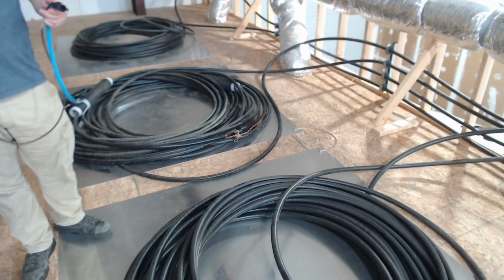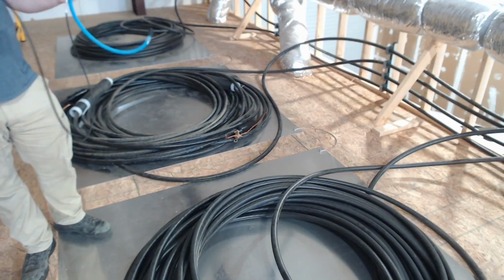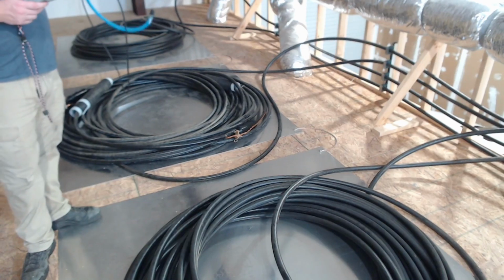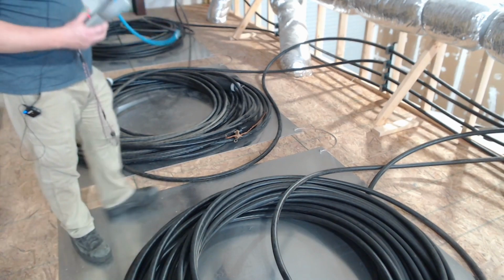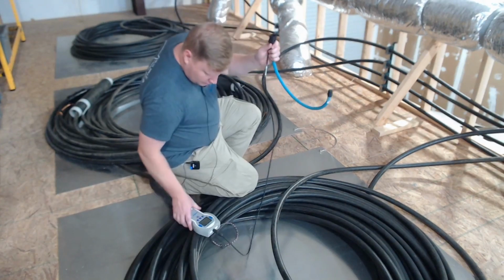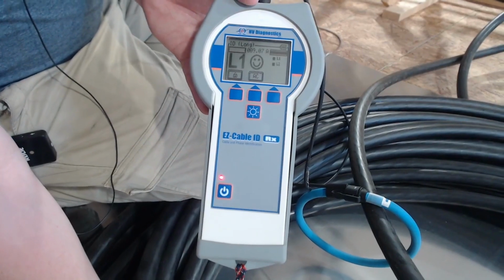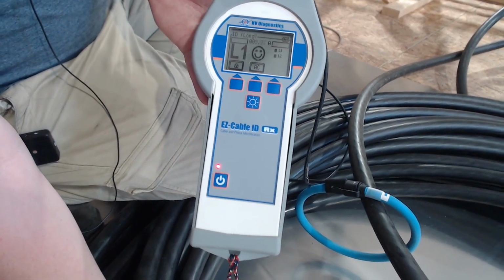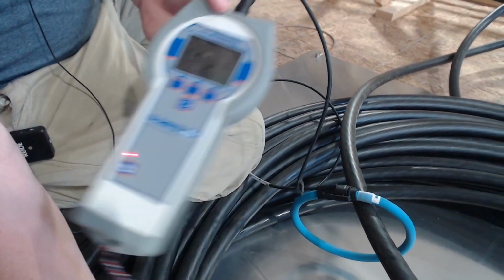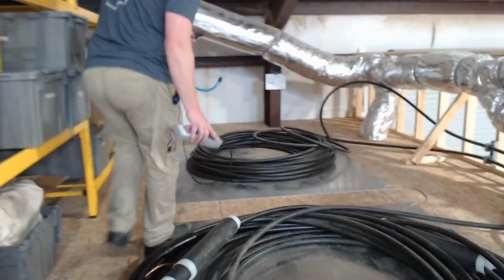So now that we're calibrated down below, we are going to come up to our unknown cables, and we're going to hook up and ID them with the calibration mode. So we're going to bring the camera over. All right, so it sees L1. Got the smiley face, so this has confirmed as L1. So now we can move on over to our next unknown cable.